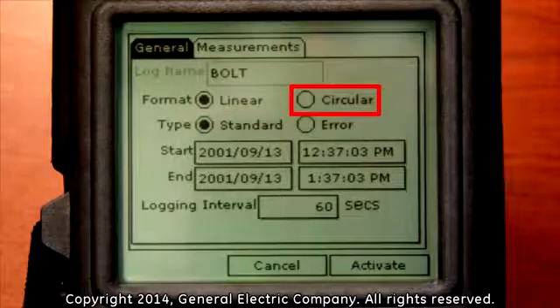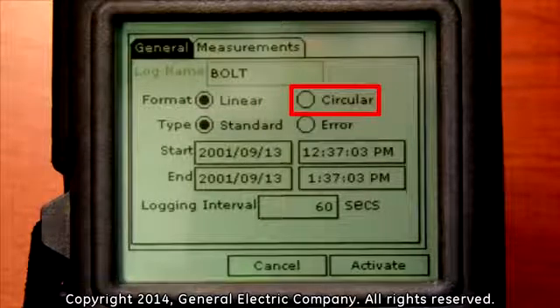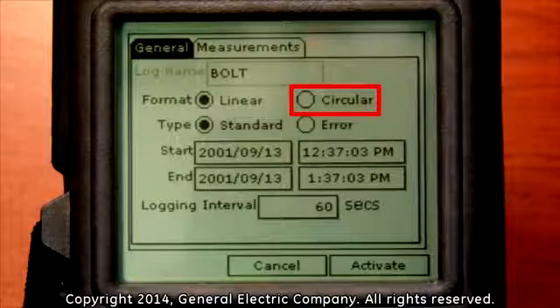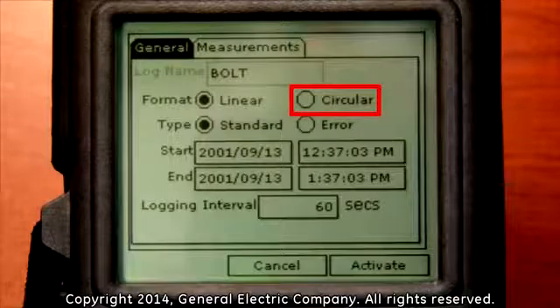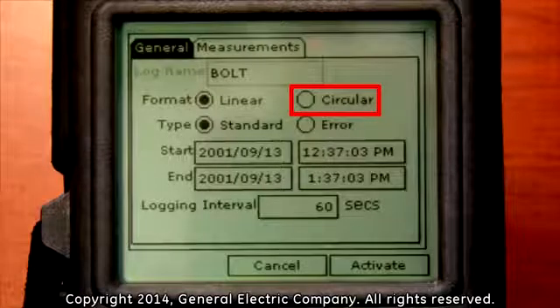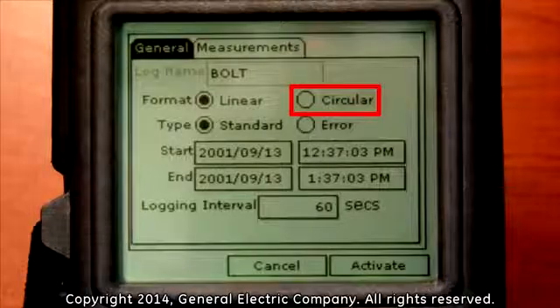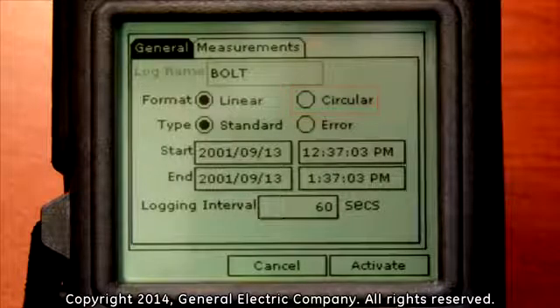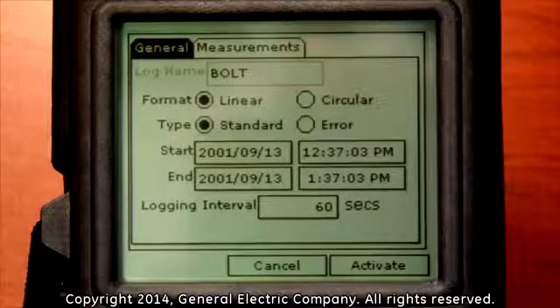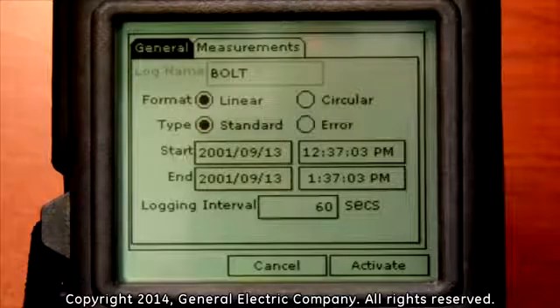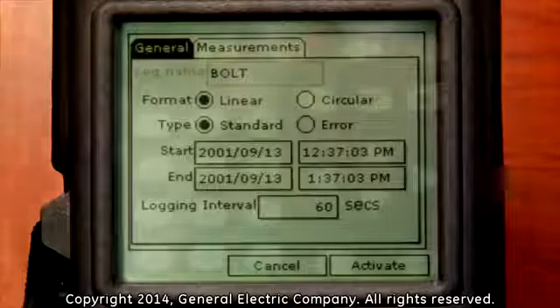The circular format is for starting data logging at a specific time, recording at specific intervals until a designated number of records are reached, and then recirculating back to start over again. For this example, we will choose a linear format with a standard type option for the logging parameters.